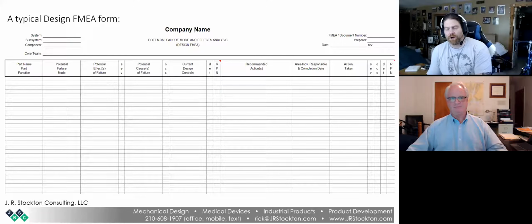If you're doing CE marking, you typically are providing design FMEAs, and when they start looking at these process FMEAs is when they come in on site and look at your production process controls and do an FDA inspection. So they look at them at different times, from different perspectives, and there are different people doing them. So even though they both end in the same 4-letter acronym, they are not the same. So keep that in mind.